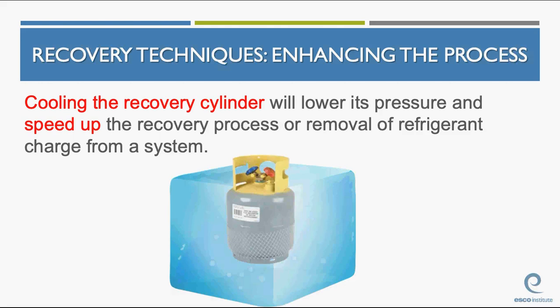The other thing you can do to speed up the recovery process is cool the recovery cylinder. Refrigerant really likes going to the colder location. Refrigerant will always flow to a cooler location. So if I cool the recovery cylinder, like putting it in a bucket of ice, I can actually speed up the recovery process. Keeping that cylinder cold lowers the pressure of the refrigerant in that cylinder, and the recovery machine has to overcome less of a pressure differential.